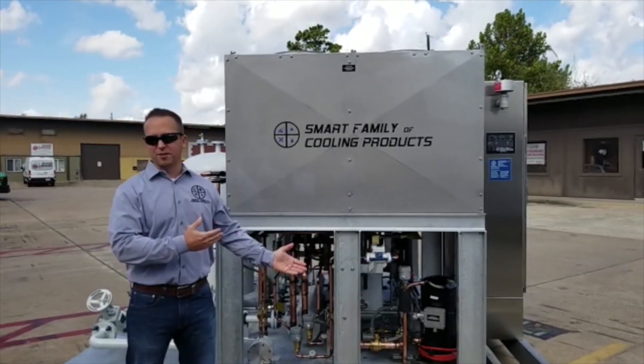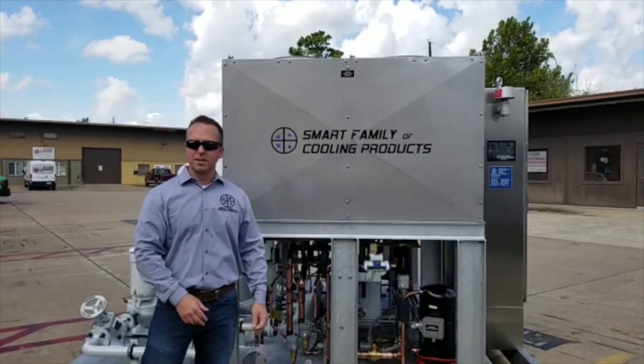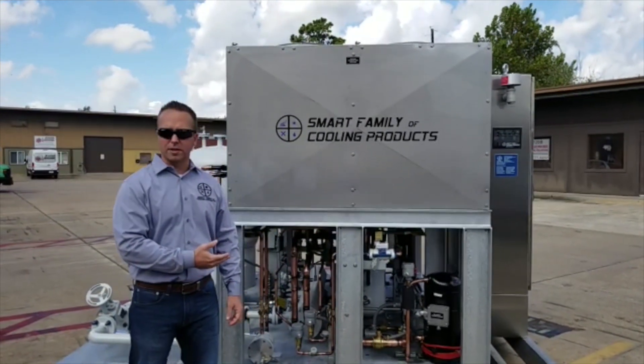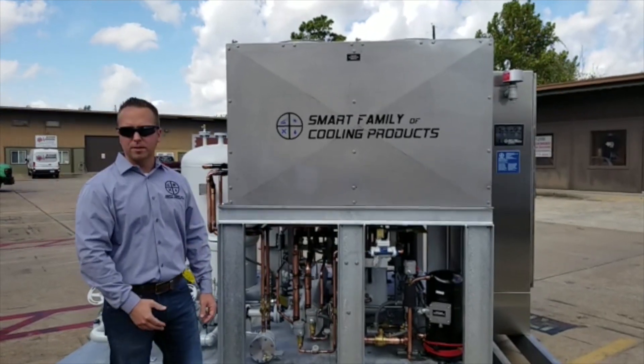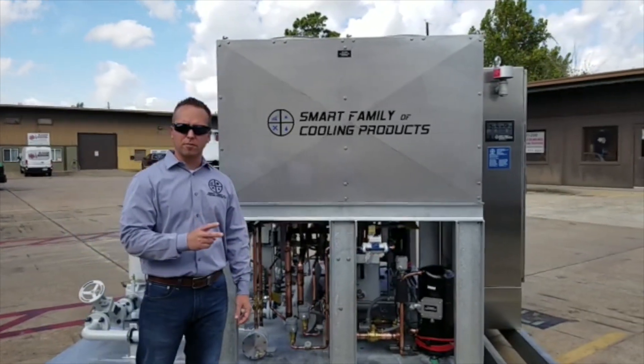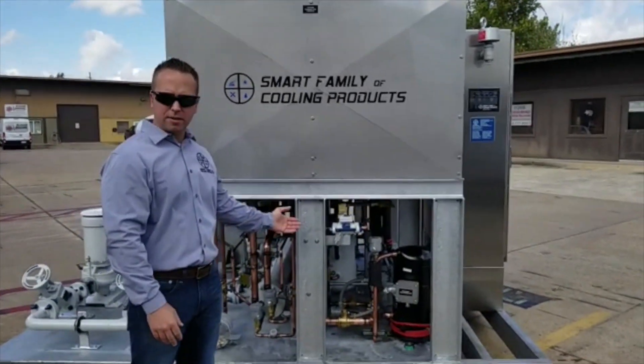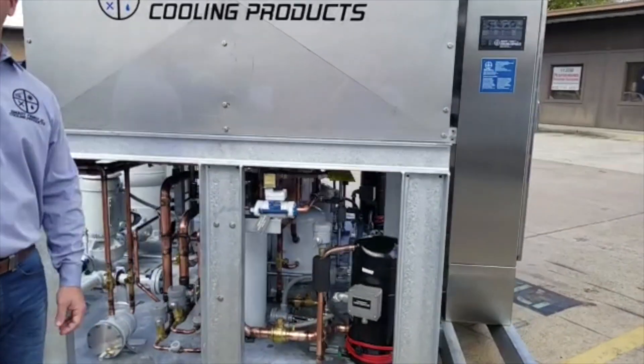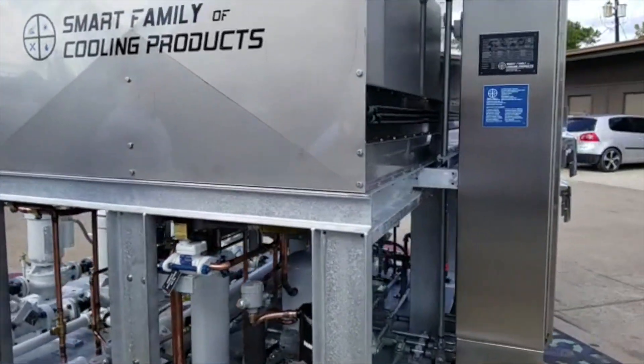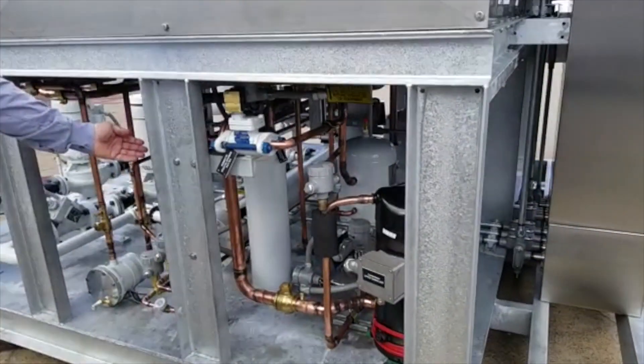So let's discuss this chiller as a whole. This unit is actually a full-process cooling solution. It's an air-cooled, dual-circuit chiller with an integral pump and tank station installed. This chiller system is composed of two refrigerant circuits, each being identical. The condenser coils are E-coated. They're 8 FPI, 0.007-inch thick industrial non-lanced fins. The refrigerant circuit has suction accumulators installed to protect the compressors.